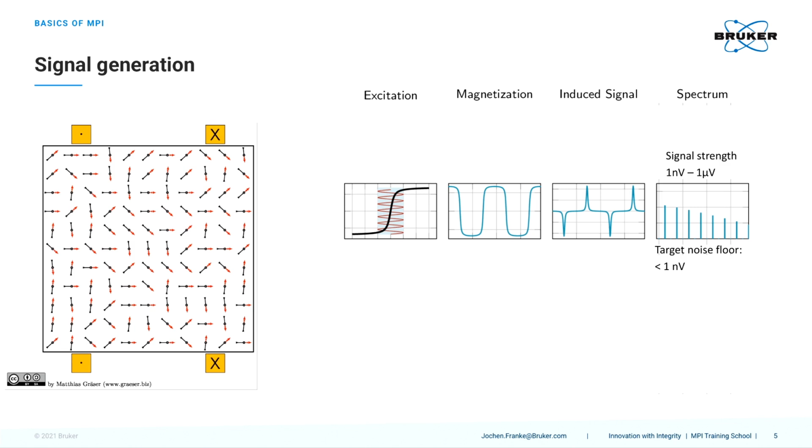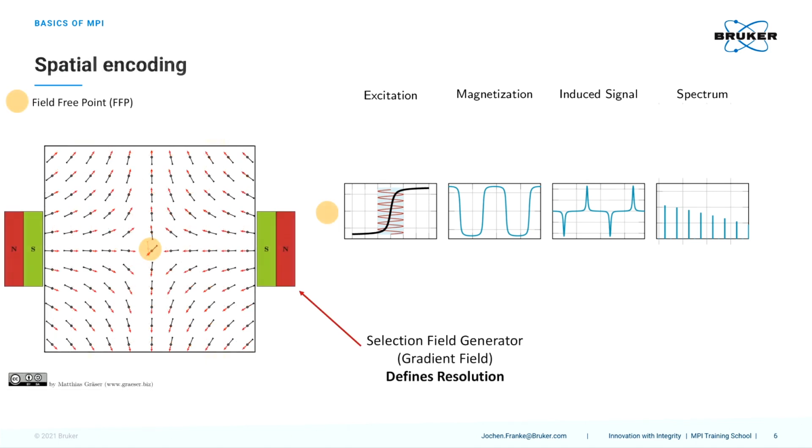But bear in mind, the particle signal itself is really, really tiny. So we are talking about nanovolts to microvolts only, and the drive field excitation is many orders of magnitude higher compared to the receive signal. So it is urgent to design the system carefully in order to measure the particle signals simultaneously to the transmit signal.